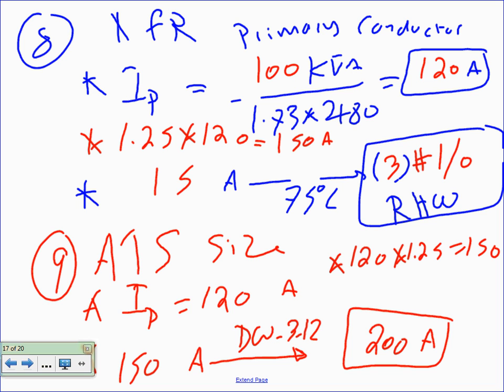Guys, sometimes the 1.25 here has to have a disclaimer. Sometimes I do it, sometimes I don't. Because remember, Chris, we already multiplied by 1.25 when we sized the transformer. So it's a lot of oversizing. Is it alright if we just do it once? Well, I used to do it once, but people lean a lot on the side of safety and so on. You're safer if you do 1.25.